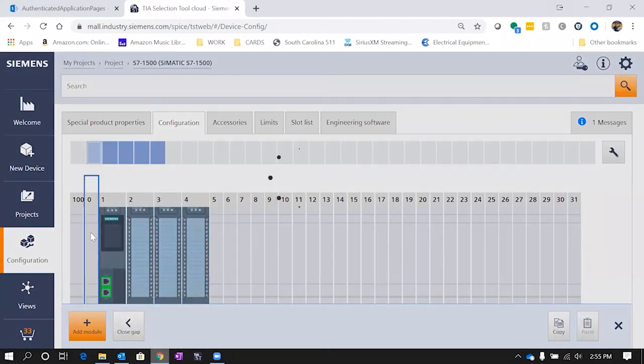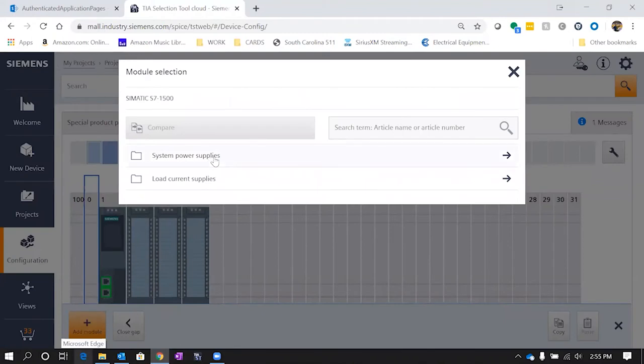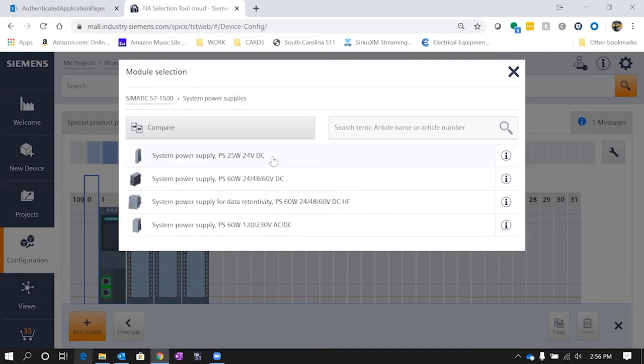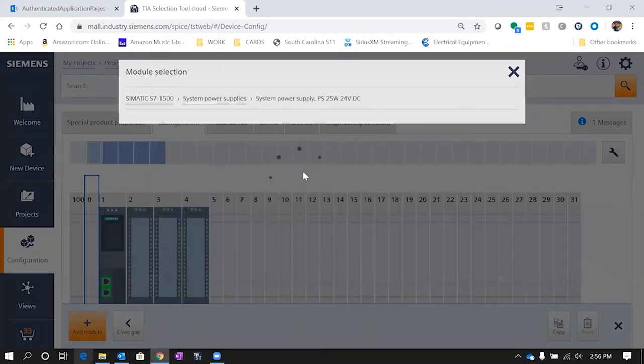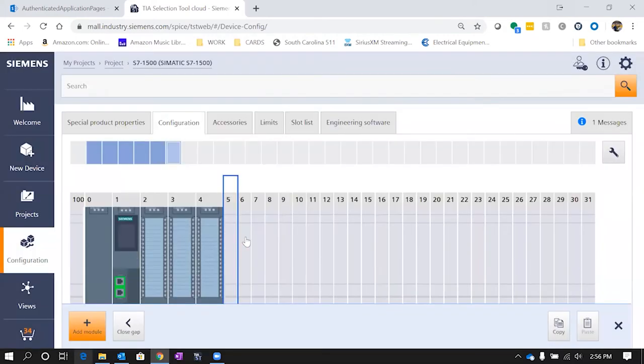All right, so now let's go to slot zero. We're going to need to enter a power supply for this unit. Unless we select a 120 direct from wall or we have a 24 volt power supply already that we want to use for this, you can get a power supply specific for that PLC. So let's just go ahead and we'll select this 25 watt 24 volt DC. So now we have that in there, we should be good to go.